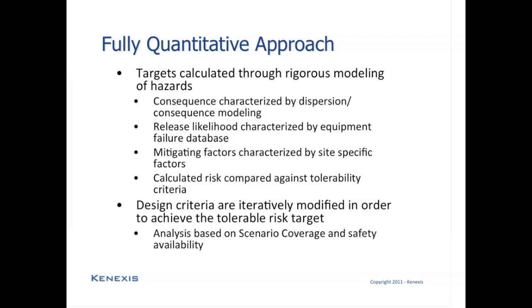Then there are also other factors of the design of the facility, such as the spacing and the type of decking used, that are going to determine the consequences that can occur. Once all these factors are calculated, there will be an overall level of risk for that zone in the facility. That calculated risk will then be compared against the various tolerability criteria that are available from that organization. If the risk is tolerable, the as-is situation is acceptable, whether the as-is situation is existing fire and gas detection equipment or no fire and gas detection equipment.